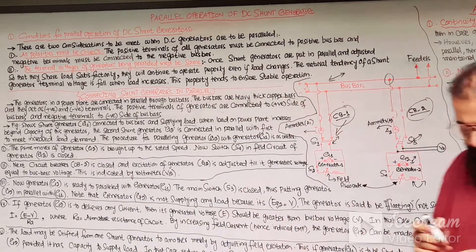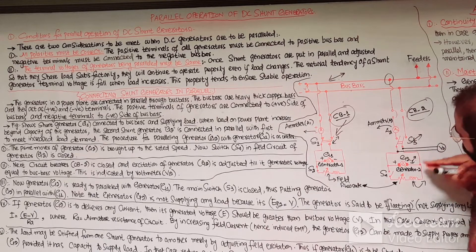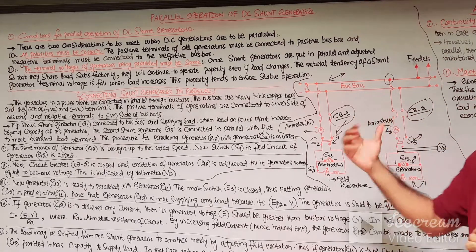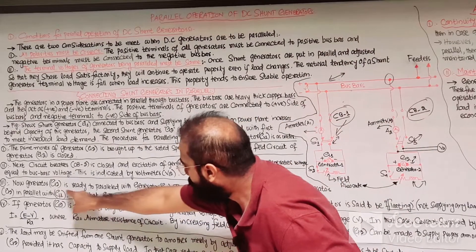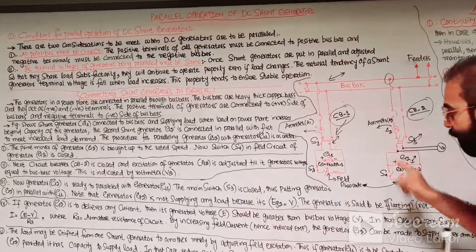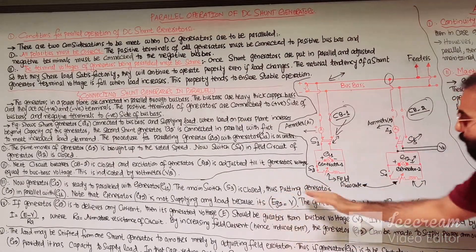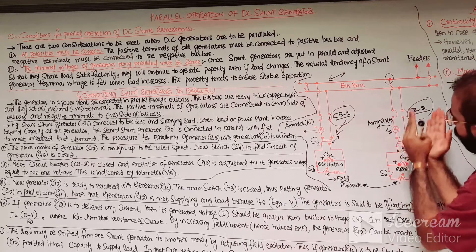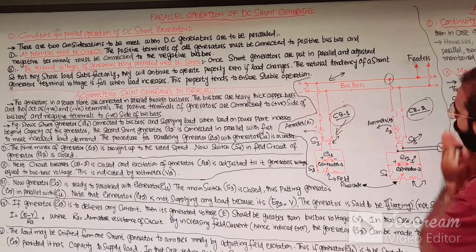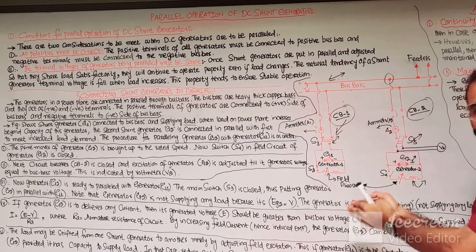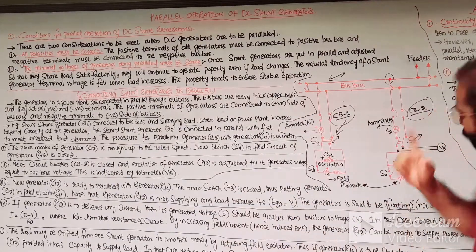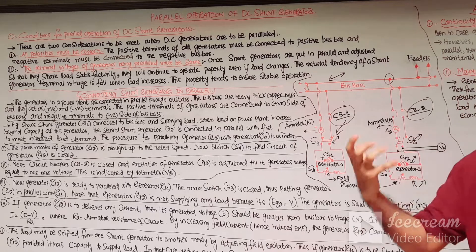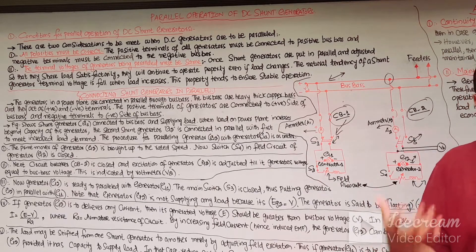The third step is that when the generated voltage of the G2 generator is equal to the bus bar voltage, G2 is ready to be connected in parallel with G1. Close the main switch S3, putting G2 in parallel with G1. When S3 is closed and the generated voltage of G2 equals the bus bar voltage, G2 is not supplying any load — this state is called the floating state.